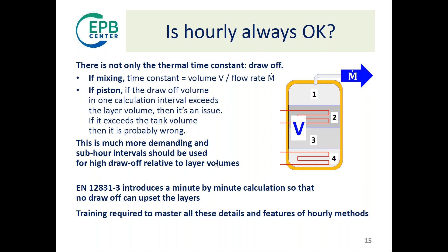This is what we have: a draw-off in 1 hour is okay, but if the draw-off is very high or the store is very small, then you have an issue. That's why, for example, 12831-3, which deals with water storage in a similar way to the energy performance calculation but for sizing purposes, uses a minute-by-minute calculation so that no draw-off can upset the layer orders. Mastering all these details requires some training and understanding of what you are doing, so this is a possible limitation.